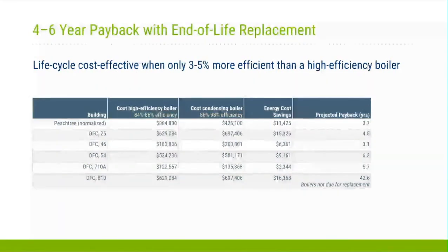Next slide. And so the economic evaluation of this technology is shown here. Essentially, one of the takeaways is that these are very cost-effective options when you're doing end-of-life replacement. So 4 to 6 year paybacks with end-of-life replacement. In some of these cases, you'll see in follow-on slides that the condensing boilers aren't providing a huge bump in efficiency compared to a typical high-efficiency boiler that's mandated by FEMP, which is what you need to put into your building if you're going to replace boilers. They might not have huge efficiency bumps, but they still provide good savings and a short payback.